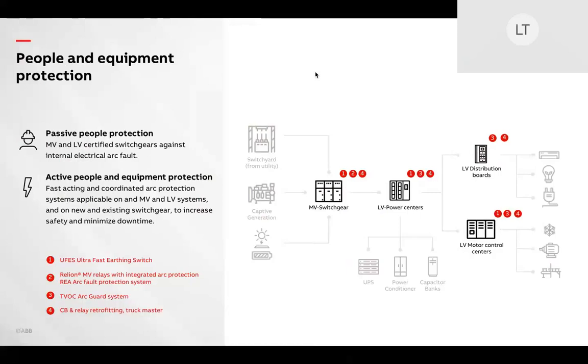Next, we have active solutions that can be built in the factory, or they can be retrofitted to existing equipment in your plants. Examples of this type of solution are ABB's ultra-fast acting earthing switch, or the Relion series of relays, which are integrated with arc fault protection. We also have the TVOC arc guard system and a full lineup of low and medium voltage circuit breaker retrofit solutions with intelligence built in.